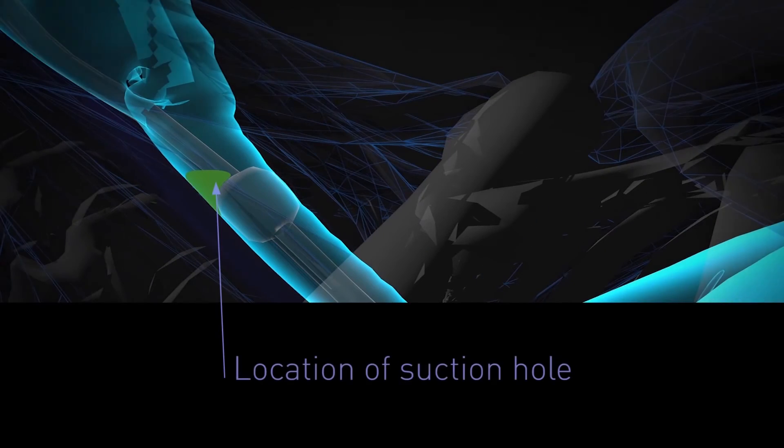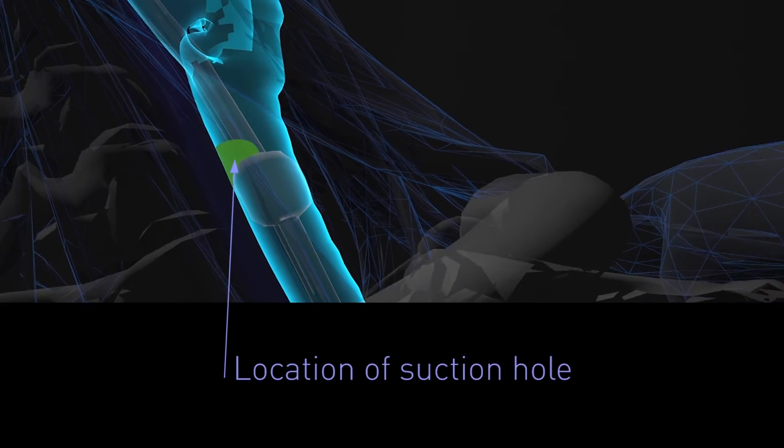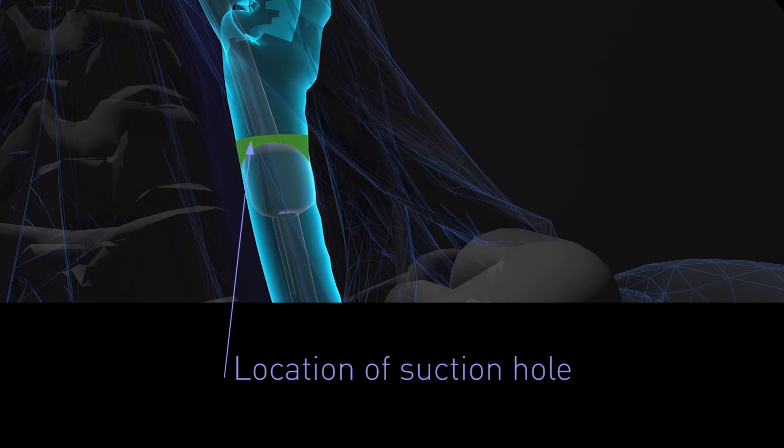The location of the suction hole above the balloon cuff can impact the amount of secretions aspirated through the suction port. In most subglottic endotracheal tubes, the suction hole is located in the dorsal position, as close to the balloon cuff as possible for maximum secretion removal.